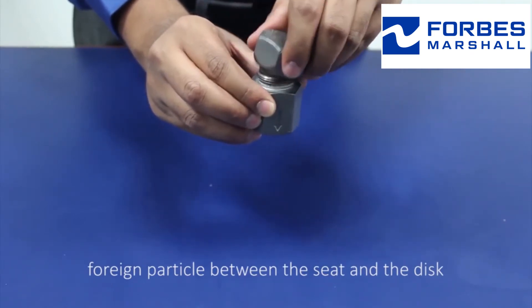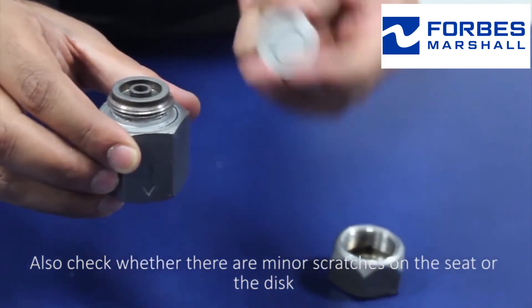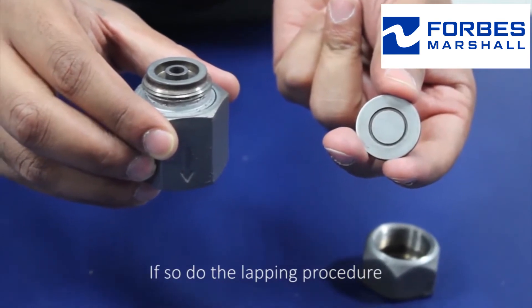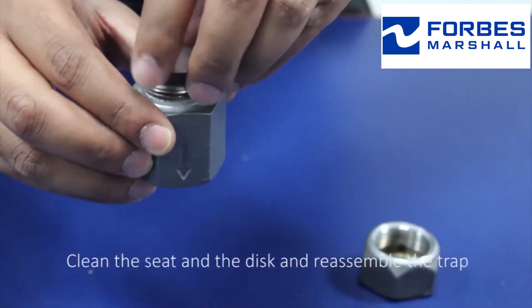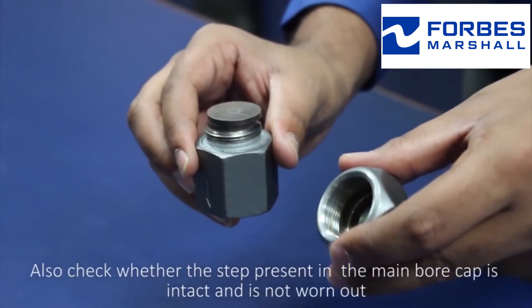particle between the seat and the disc. Also check whether there are minor scratches on the seat or the disc. If so, do the lapping procedure, clean the seat and the disc, and reassemble the trap.